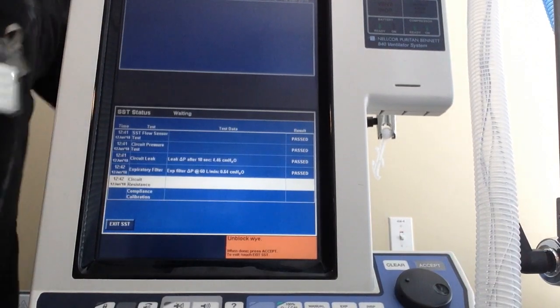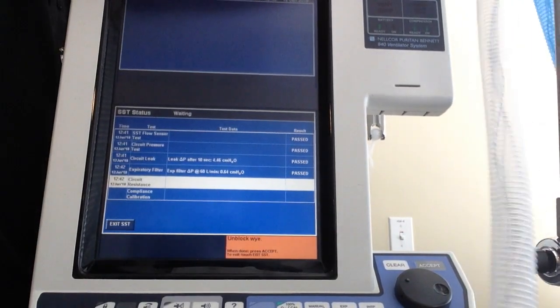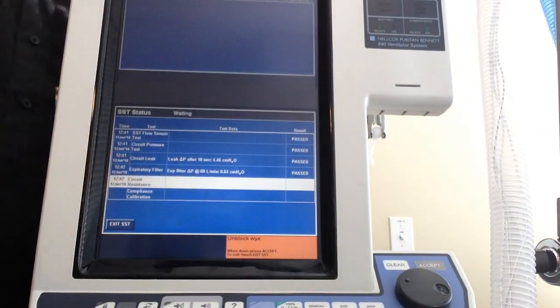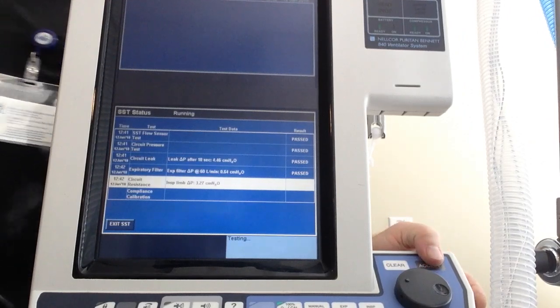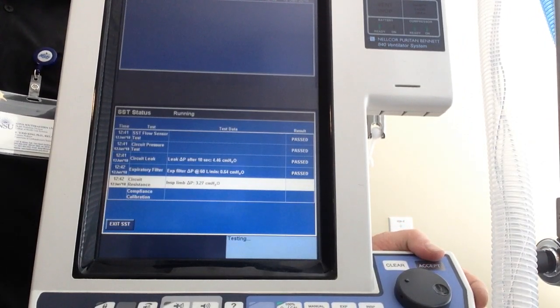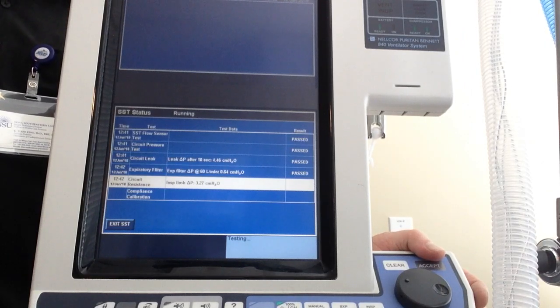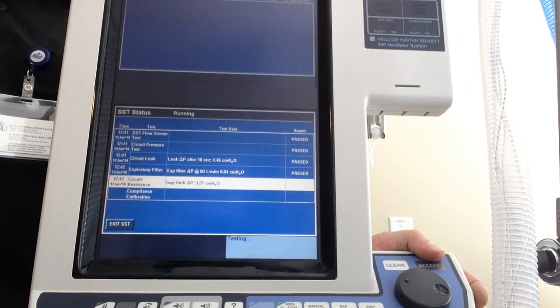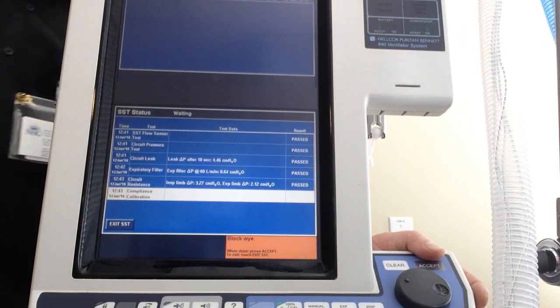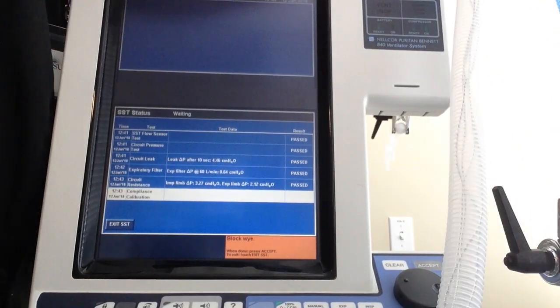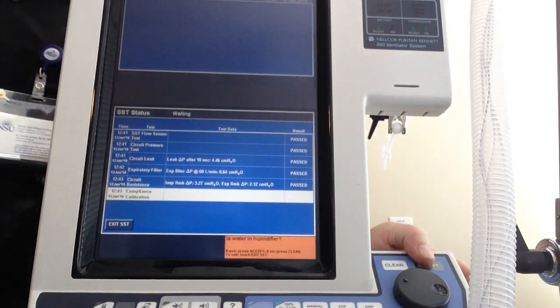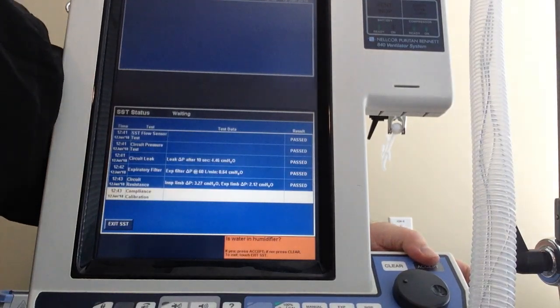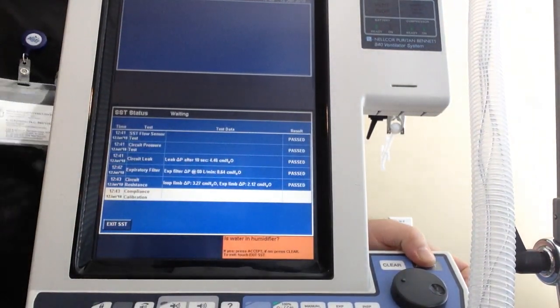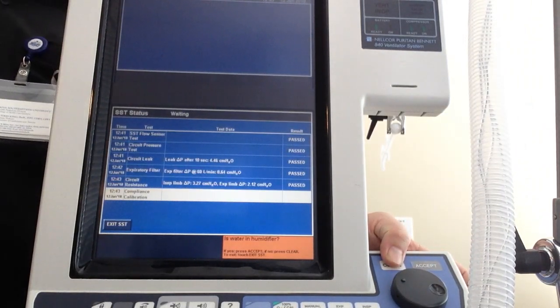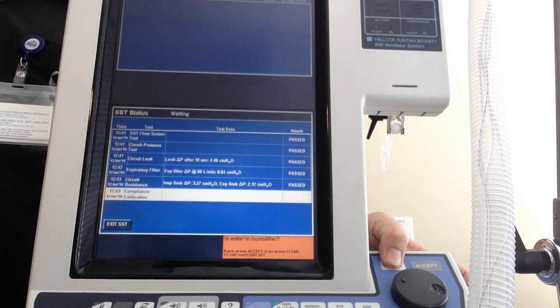Then it says to unblock Y. So I'll unblock my Y and hit accept. Then it says block Y. So I'll put the elbow back in, hit accept. Then it asks if there is water in the humidifier. No, there is not, so I'm going to hit clear. If I hit accept, that says water's in there. If I hit clear, that means no water is in the humidifier.